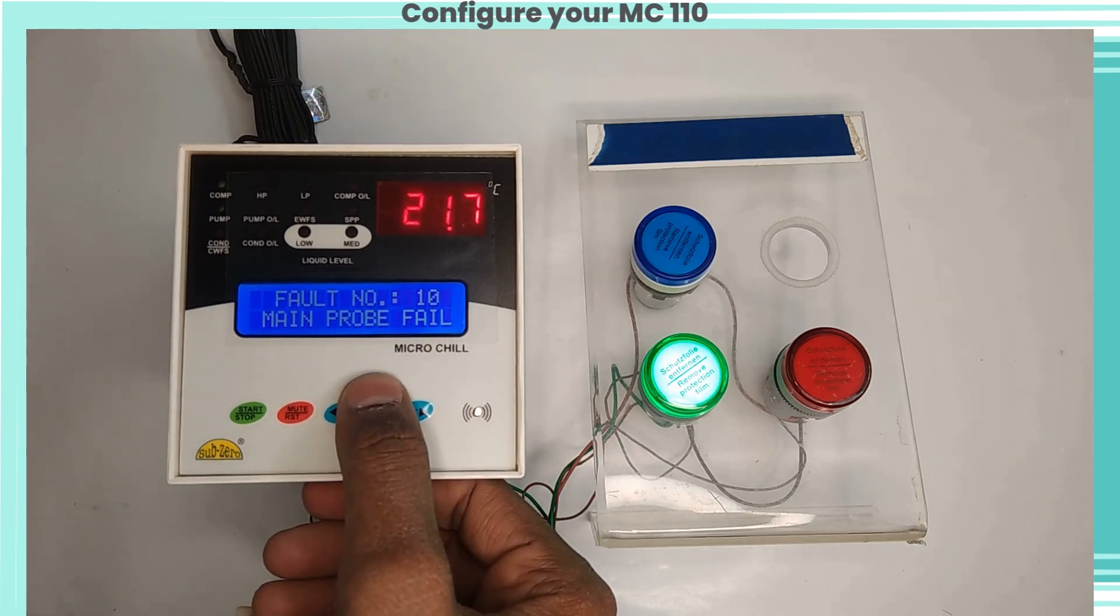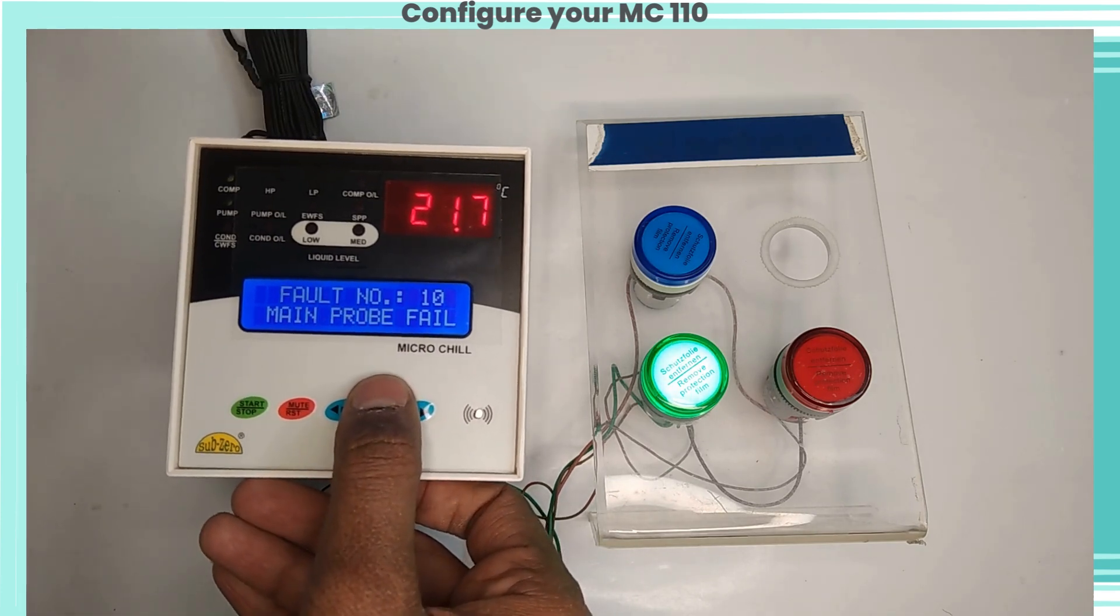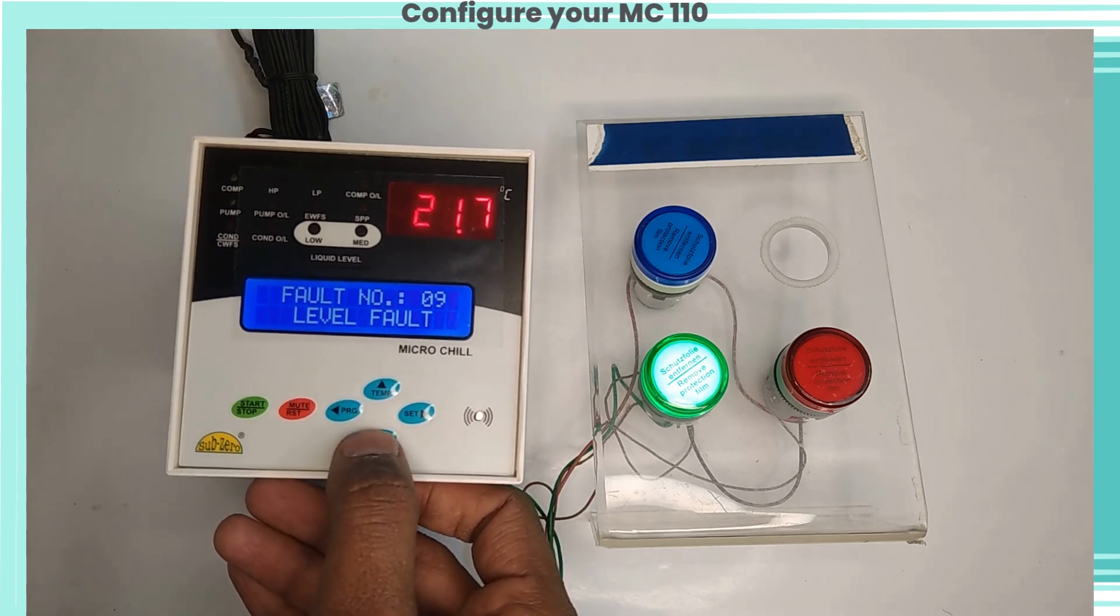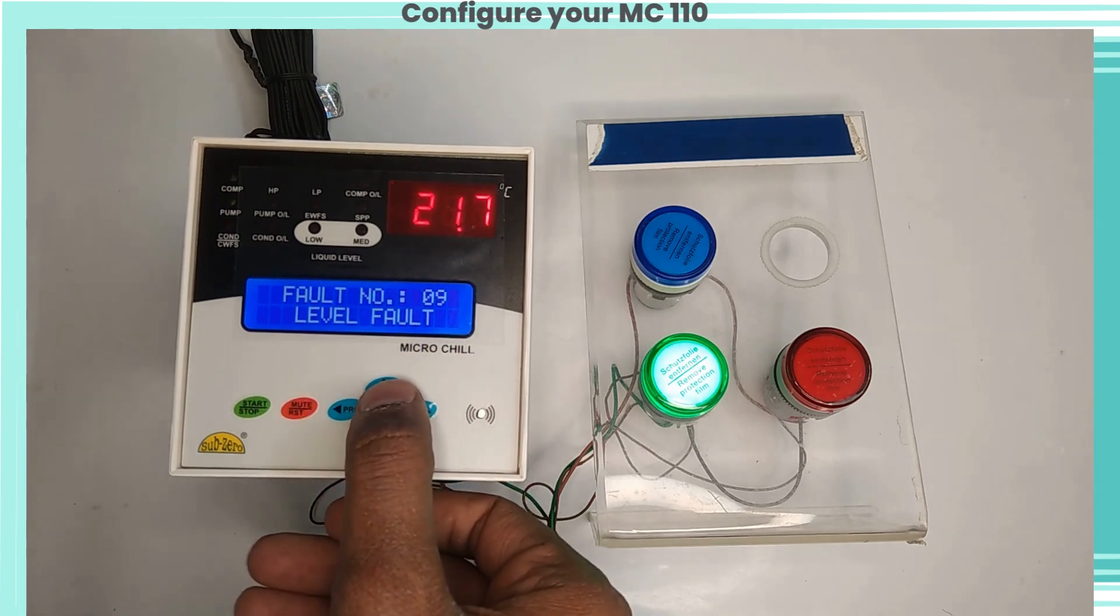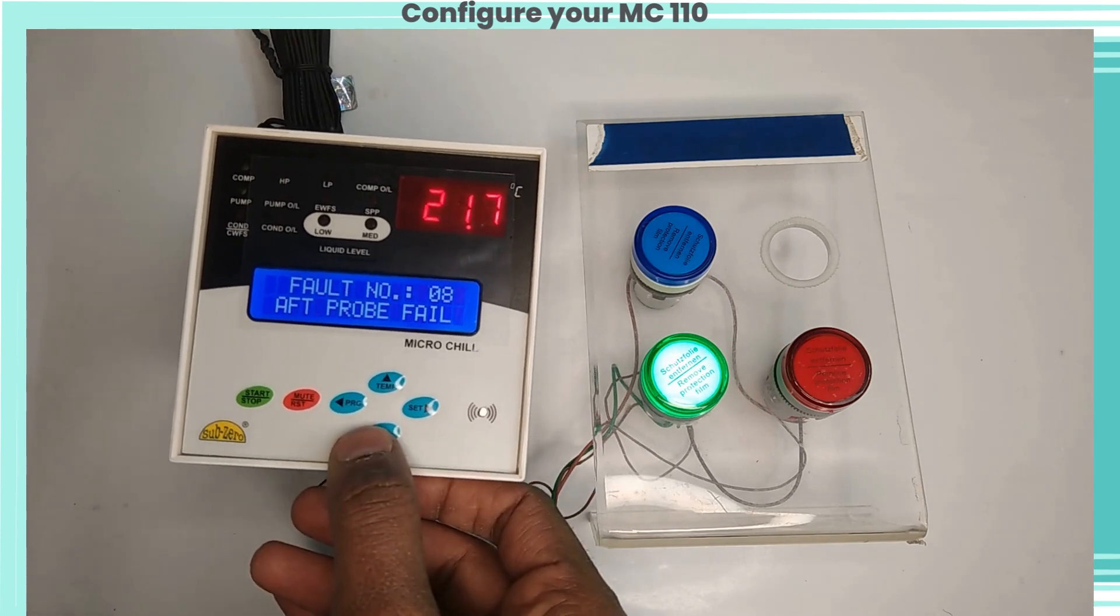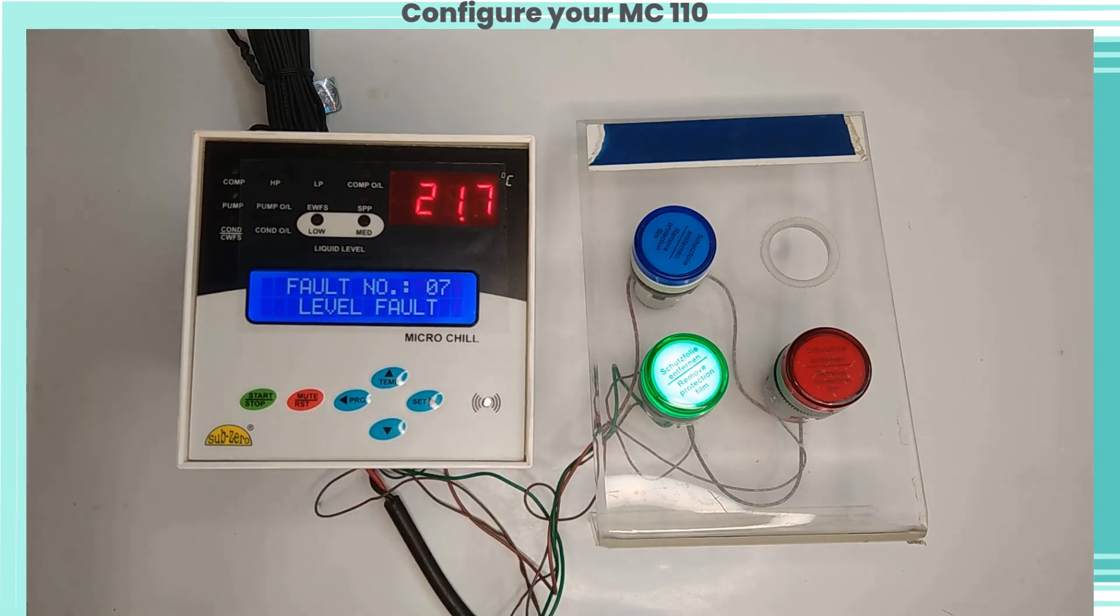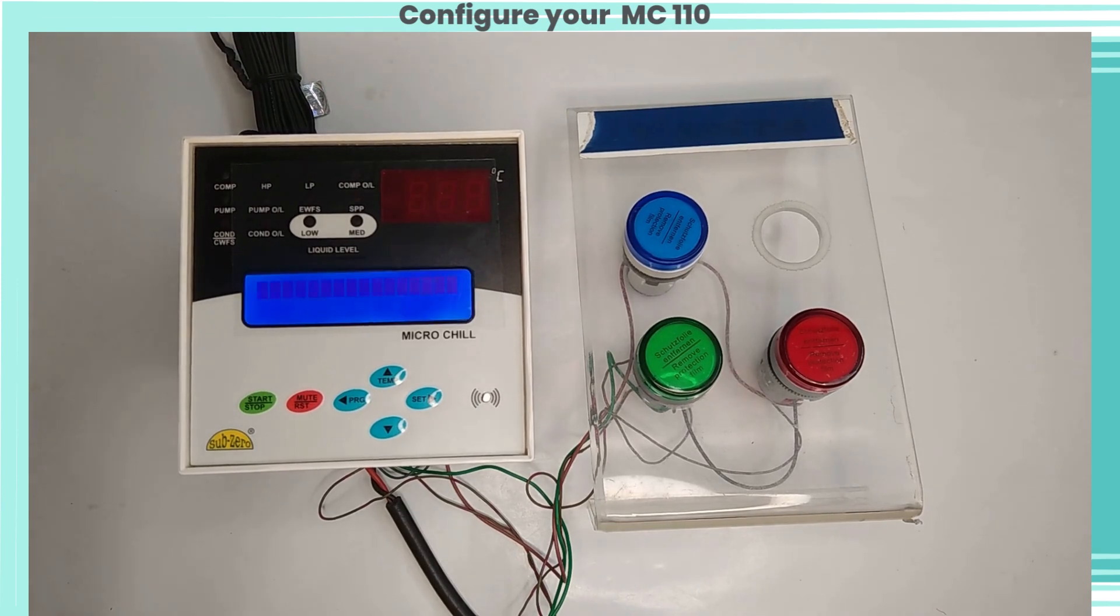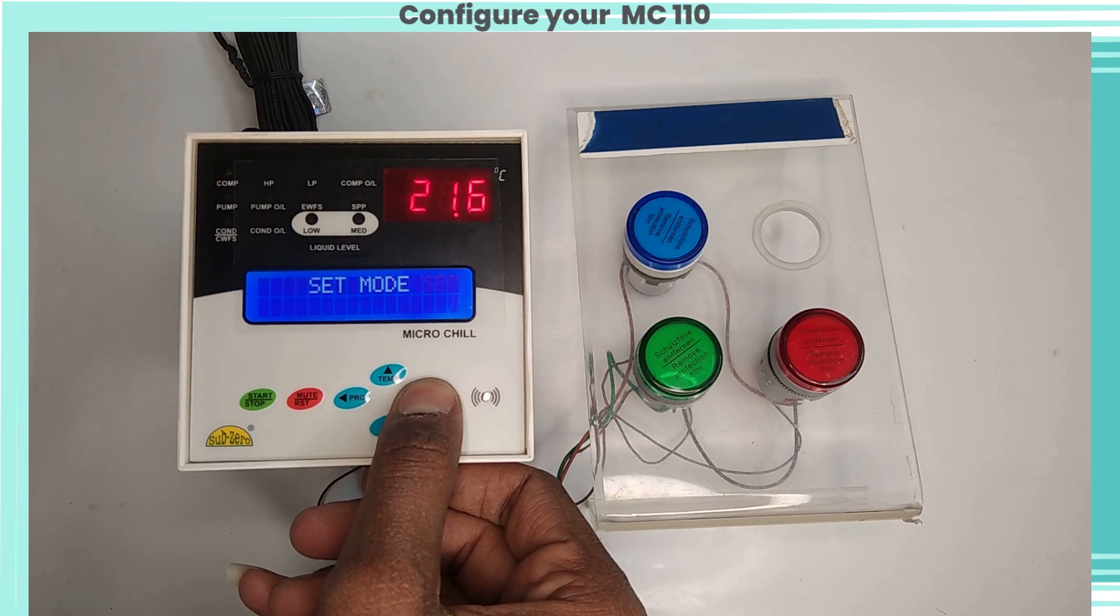If fault number 10 appears, then main probe fail. If fault number 9 appears, then level fault is there. If fault number 8 appears, then AFT probe fail. If fault number 7 appears, then level fault is there. Now let's configure the device and check the fault status. Here we haven't connected any probe for temperature sensor or any level sensor, so we will get different types of fault error logs. Let's check it.